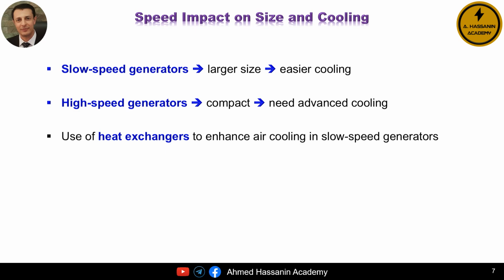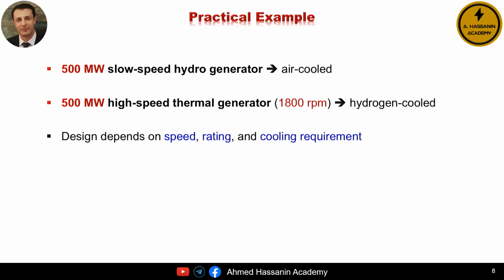Now compare that with high-speed generators. These machines are much more compact, which is great for saving space, but thermally it's more challenging. The smaller size means less surface area, so heat builds up more quickly. That's why high-speed generators usually require more advanced cooling methods, such as hydrogen cooling or even direct water cooling. So the key idea here is this: speed affects size and size affects cooling. Slow-speed machines are bigger but easier to cool, while high-speed machines are compact and efficient, but they demand much more careful thermal design.